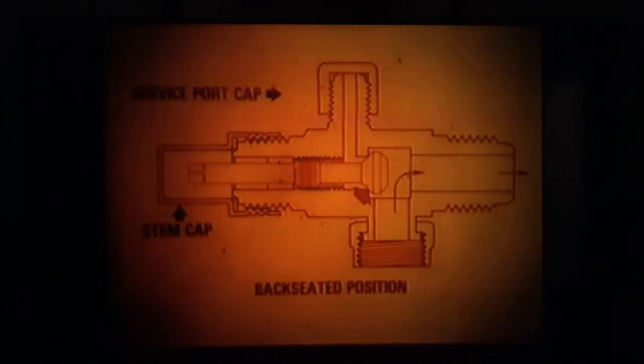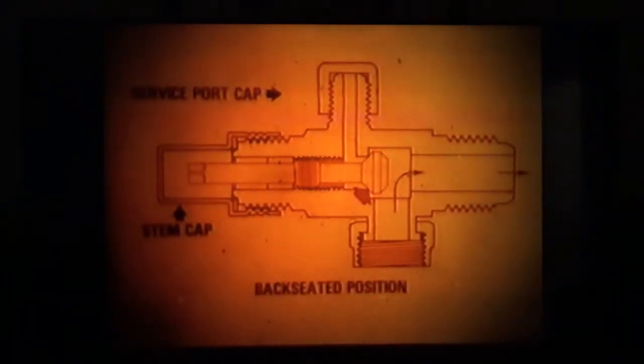Everything inside checks out. Now I'll recheck the refrigerant lines. The line to the condenser is heated up and the line from the evaporator is cold. Since everything else checks out, this may indicate excessive moisture in the system. To verify the diagnosis, I'll connect the service hoses from the portable air conditioner service station and check the operating pressures. To check the operating pressures, remove the caps from the compressor service valve stems and check to see that the stems are in the back-seated position. Then remove the caps from the compressor service valve ports.